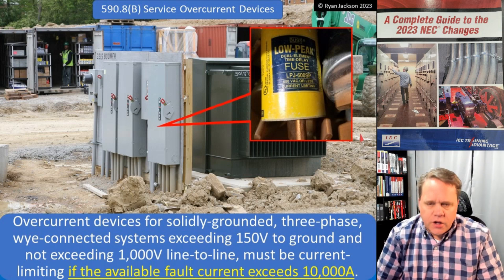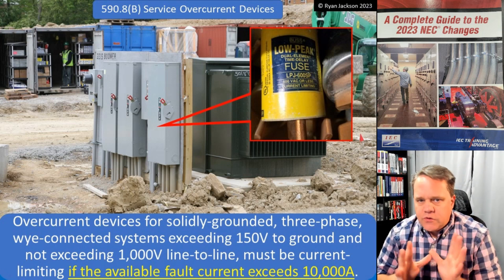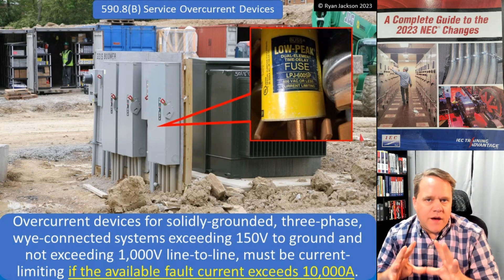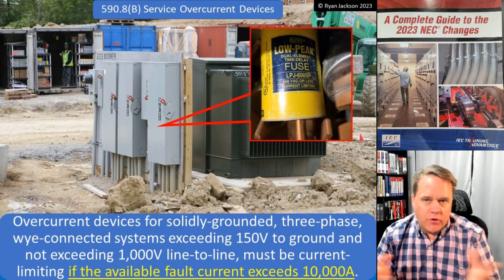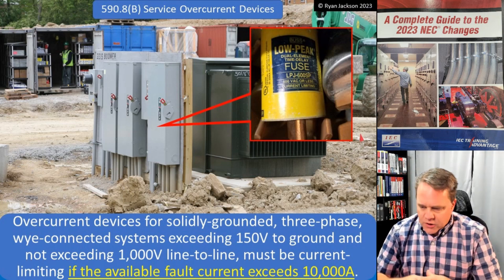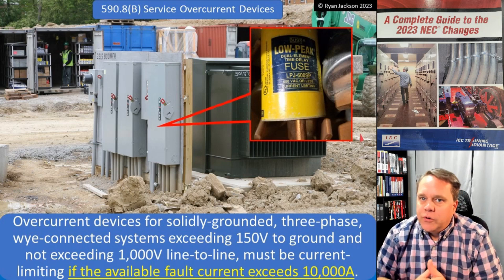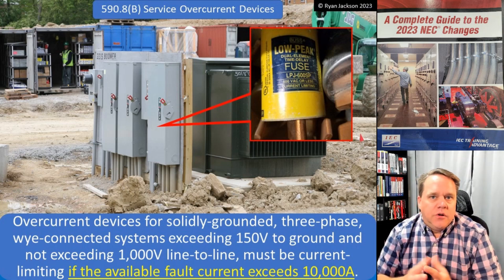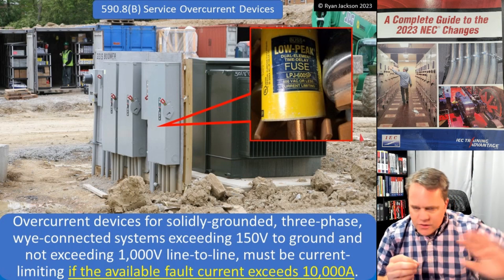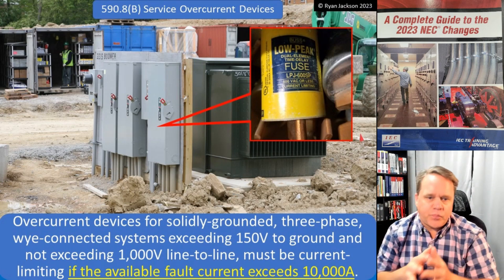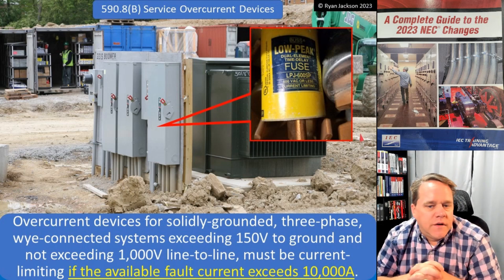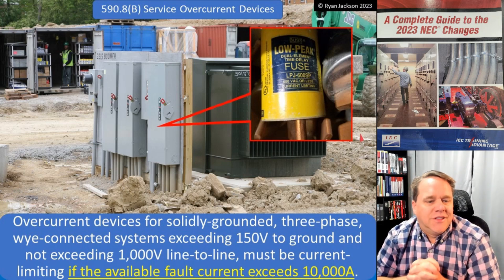We're going to go through this one slowly. Number one: service overcurrent devices. This only applies at the service. So if you have a temporary wiring installation — remember, temporary wiring can be as small as a little 50-amp outlet for building a house, or it could be absolutely massive. I've seen temporary wiring that's thousands of amps for a big high-rise building. So here we're talking about the service overcurrent device — nothing downstream of it, just the service. Overcurrent devices for solidly grounded, three-phase, Y-connected systems exceeding 150 volts to ground, not exceeding 1,000 volts line to line.